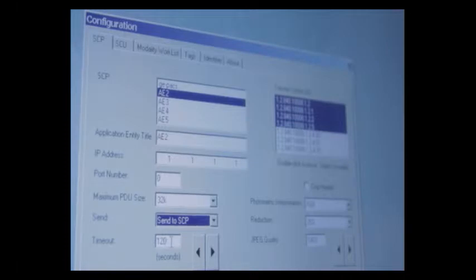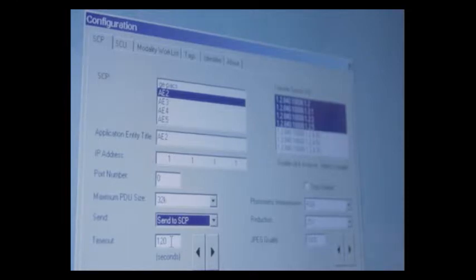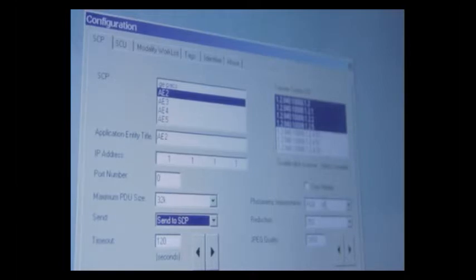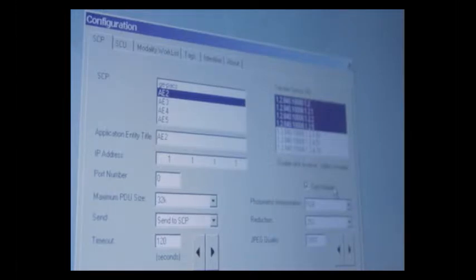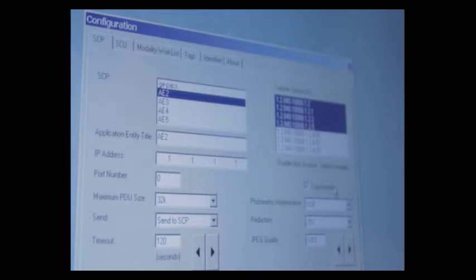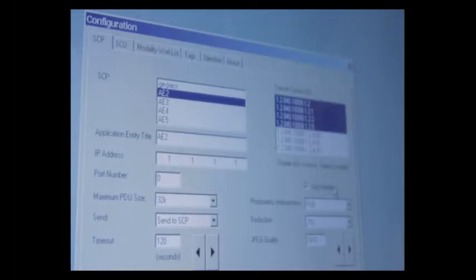Moving along, timeout is how long the machine will try to send information to your PACS system. If you don't want to wait, you can set this to, say, 60 seconds. If you want to crop the header, that will take the patient information out. Sometimes for research or a PowerPoint presentation, you don't want to display the patient name and data. If you crop the header, that will knock that information out.